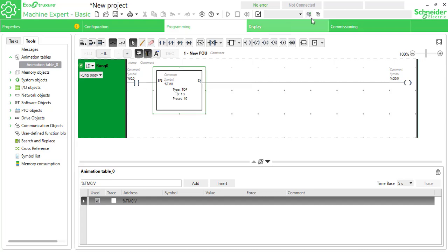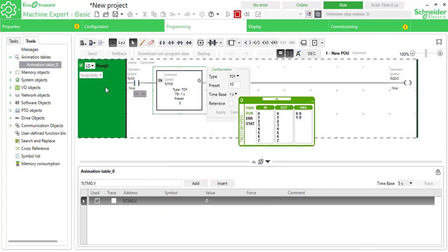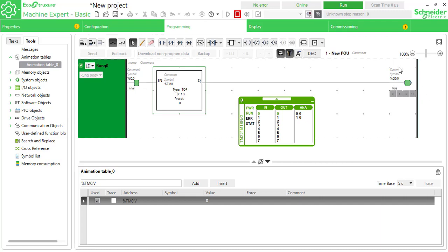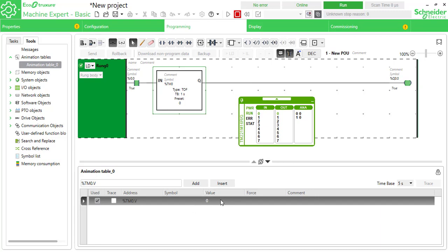Changing to off timer, removing retention, applying, and going to runtime. Start the controller. For the off timer, put it on first — the output is on while input is on, but the timer is not running. When you turn it off, you'll get output for 10 more seconds — that is the off-delay timer.